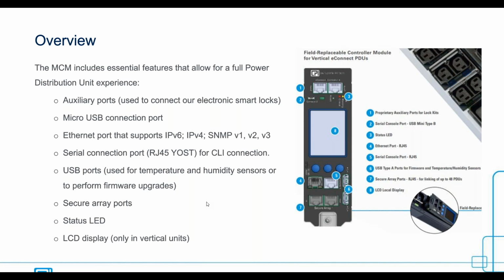To do this, it uses multiple components, such as the ones shown here on the slide. We have the auxiliary ports. These can be used to enable our electronic smart locks for the cabinet, a micro USB connection, an Ethernet port that will support IPv6, IPv4, and SNMP, a serial connection port for CLI connection, and USB ports that can be used to connect temperature and humidity sensors. The USB can also be used to perform firmware version upgrades locally on the PDU. It will also have the secure array in and out ports to connect the PDUs.